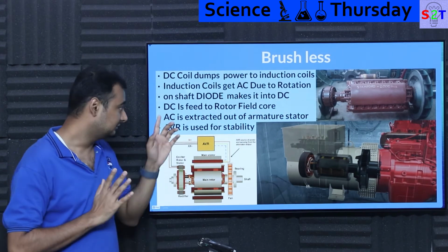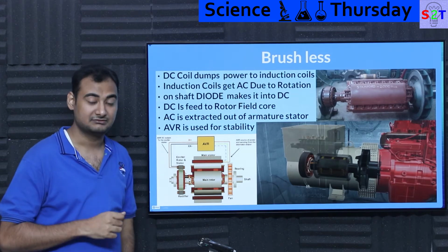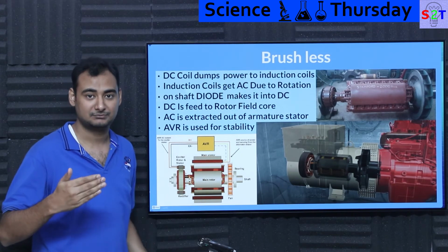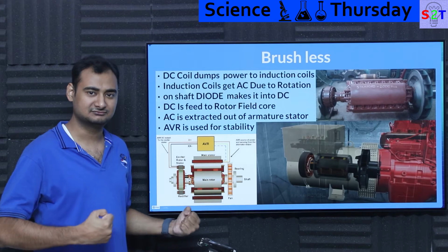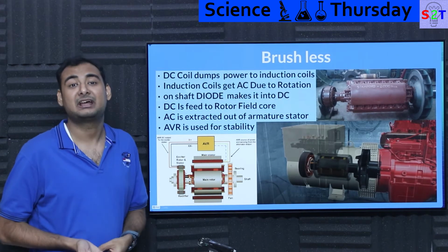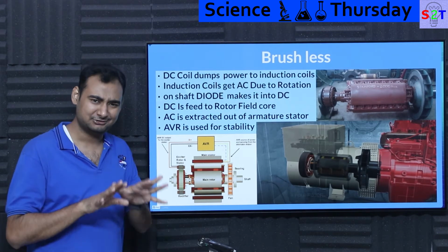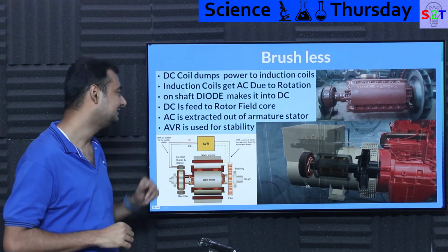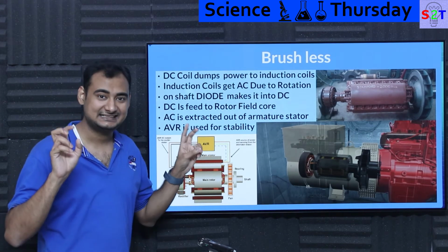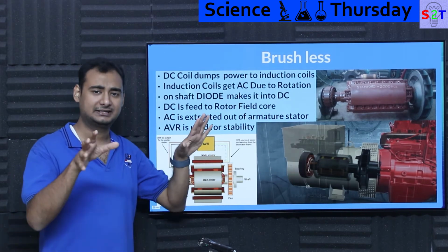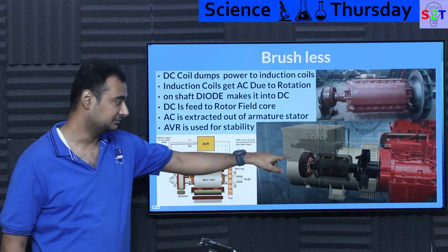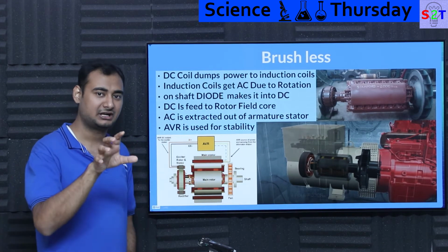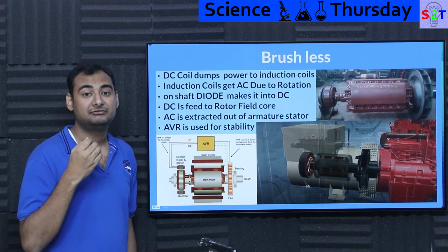So it works. The DC feed lets you control the system. For example, let's say your generator starts going high RPM with no load on it. You want to calm it down, so you control the excitation current, the core current, sending less DC to calm it down. That gives you feedback control.